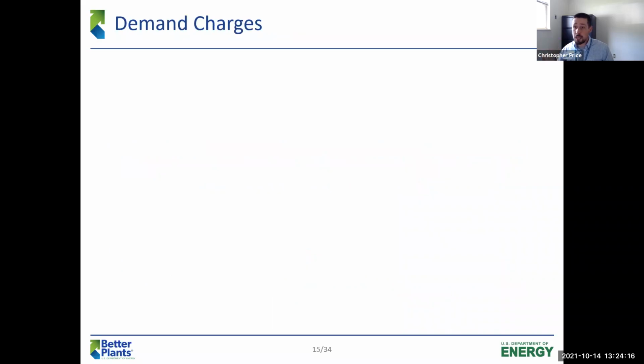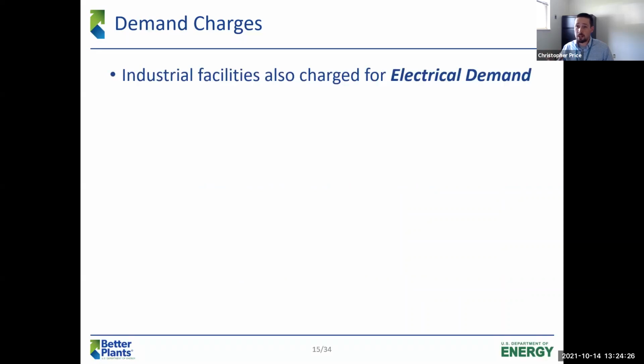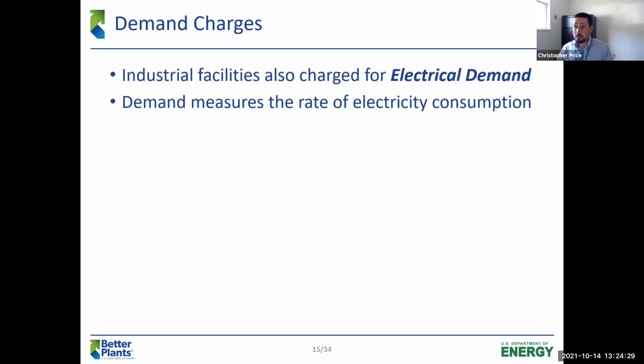Moving on to demand charges - we talked about how much energy you use in kilowatt hours. Industrial facilities and a lot of large commercial facilities are also going to be charged for their electrical demand. Demand measures the rate at which you consume electricity. So a facility that uses X amount of power, but spread out over the day, the utility doesn't have to build as much infrastructure. They don't have to put in bigger electrical pipes for a company that uses X kilowatts in a very short amount of time.